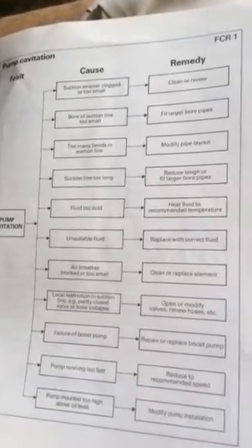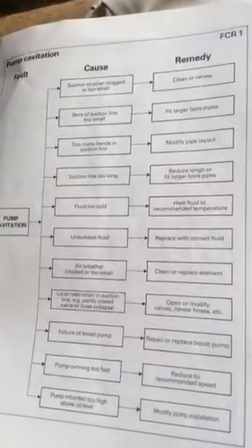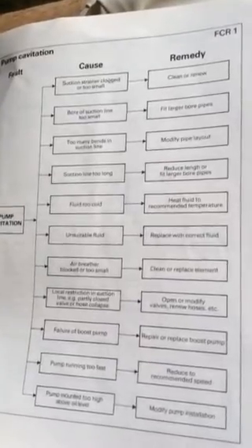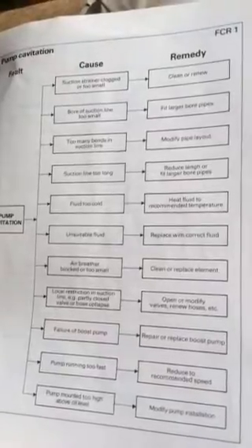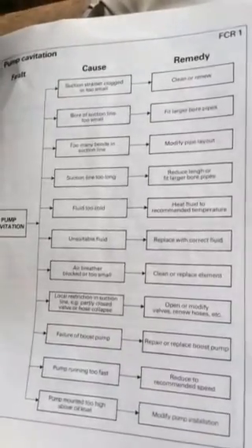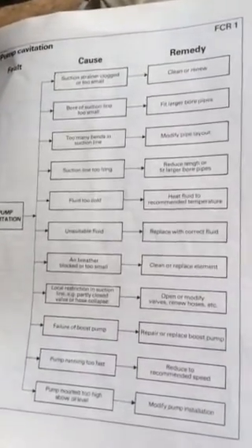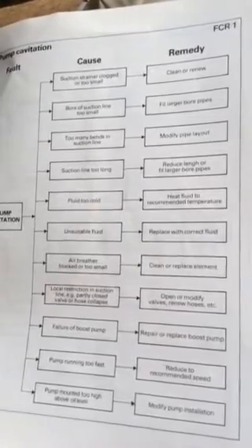Bore of suction line too small. What's the remedy? Fit large bore pipes. Too many bends in suction line, modify pipe layout. Suction line too long, reduce length or fit larger bore pipes.